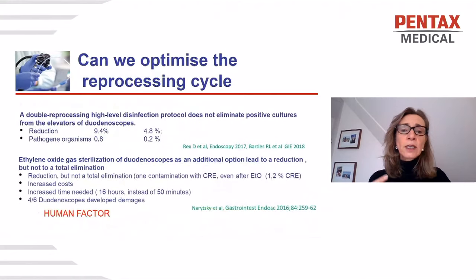Can we optimize the reprocessing cycle? A double reprocessing with high-level disinfection - we see a small reduction, but it's not zero. We're looking at ethylene oxide gas sterilization, but again, increased time is needed. So is that the solution? Probably not. Again, the human factor is really important in this reprocessing cycle.